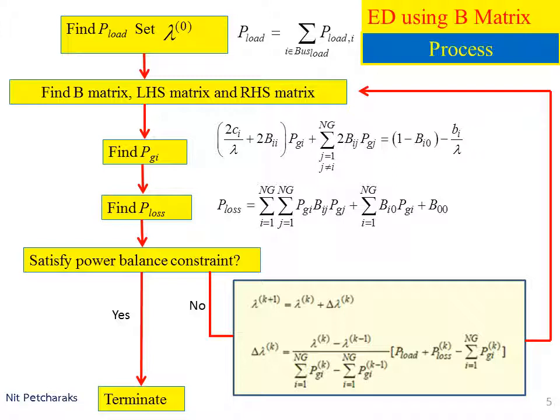Then find B matrix, LHS matrix, and RHS matrix. We will use them to find P_GI and P_loss by these equations. Then we check power balance constraint. If it is not satisfied, update lambda and go back to recalculate B matrix, LHS matrix, and RHS matrix. We will perform this process iteratively until power balance constraint is satisfied, then the process is terminated and solutions are obtained.